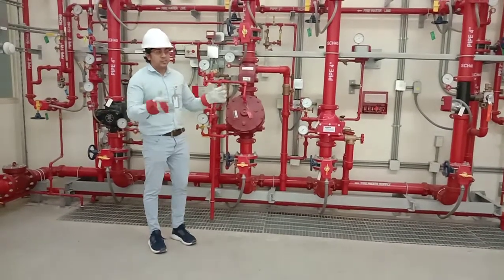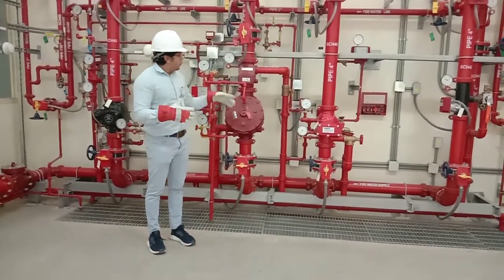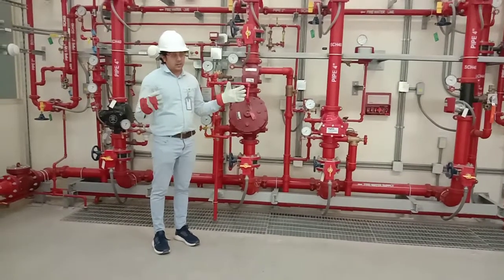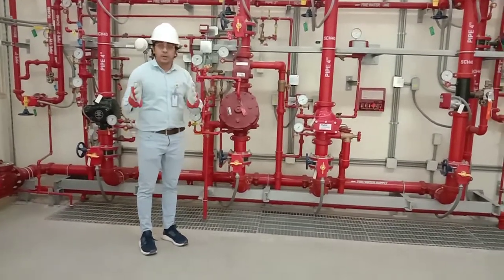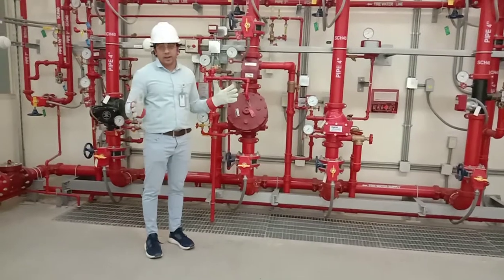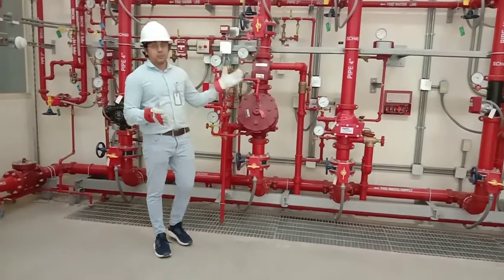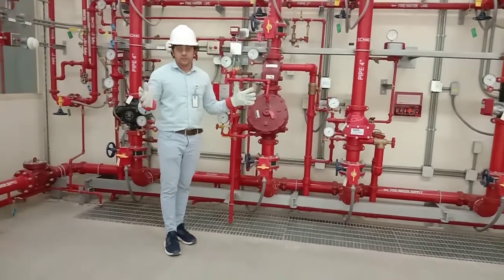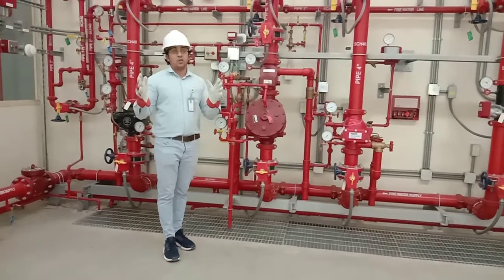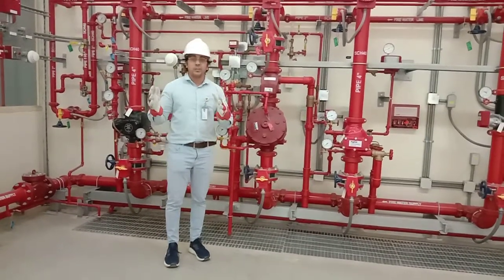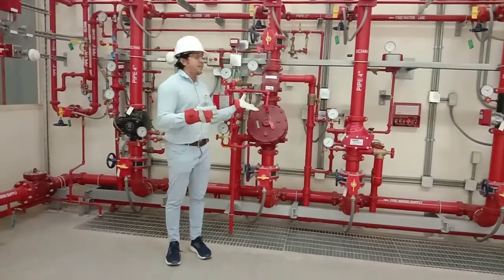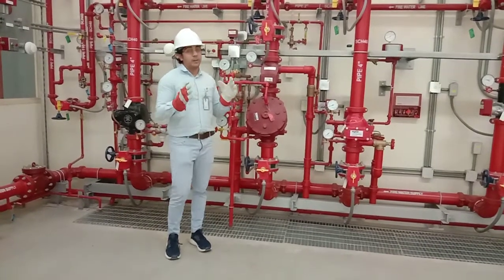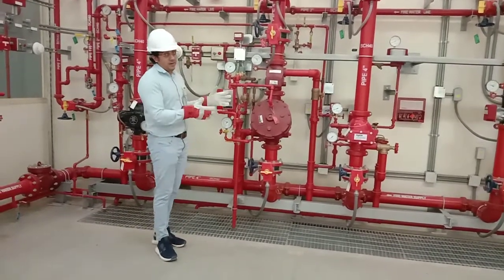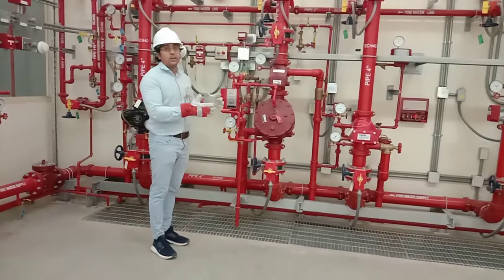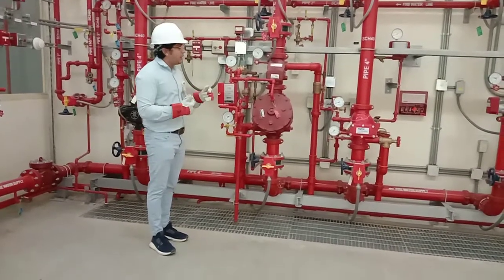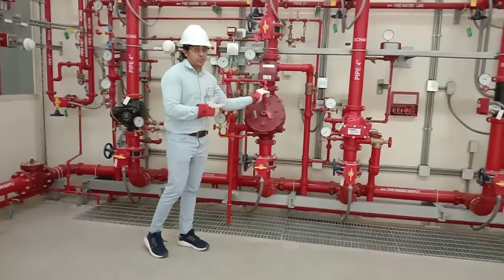Now, let's imagine there is a fire, right? Things are getting damaged due to the fire. At that moment, we can discharge the water. But without fire, if you are discharging water, it will damage those things. Like I said, in a museum, where they have stored costly items, very old items, precious items, they may be destroyed by water. So we want to make sure that only if there is an actual fire will this system activate. Otherwise, we need a different kind of philosophy.